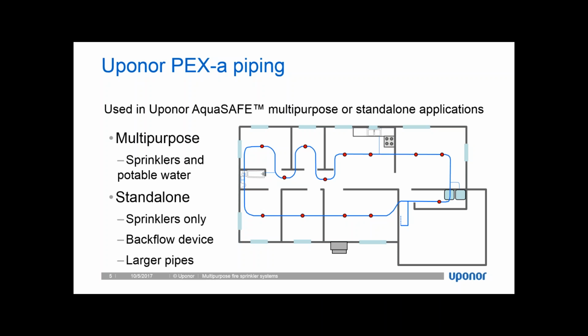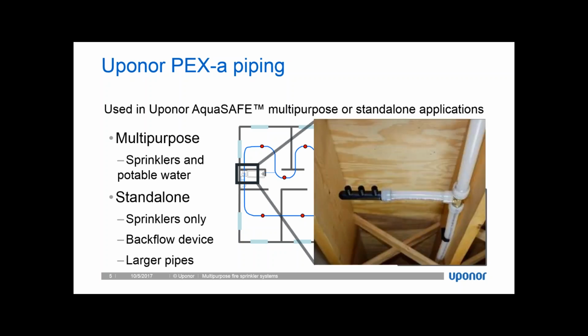So this is an example of a multi-purpose system. It looks like a piping system where we're running a big loop around the perimeter of the house and picking up all of the sprinklers as we go. Not only that, when we pass by a bathroom group, and I've highlighted the bathroom on the left-hand side of the plan, we'll pull off of that sprinkler line to a T or a multi-port T or directly to a fixture that supplies all of the plumbing fixtures in that room. So on this image, I have an Uponor multi-port T, and I would pull off of that to supply the water for my toilet or to my bathroom sink or to the shower. This uses both piping systems to do two jobs: a small amount of piping for the plumbing system to pick up the plumbing fixtures, and a majority of the pipe is supplying all of the needs for the fire sprinkler system.